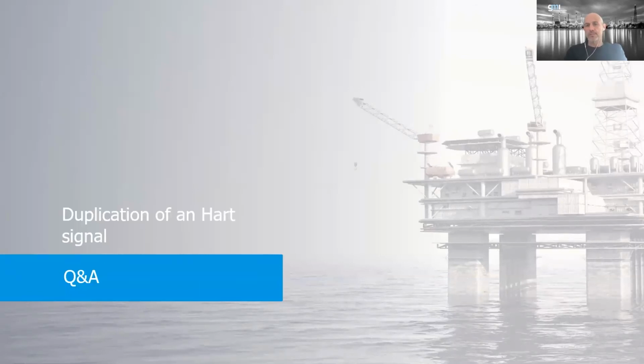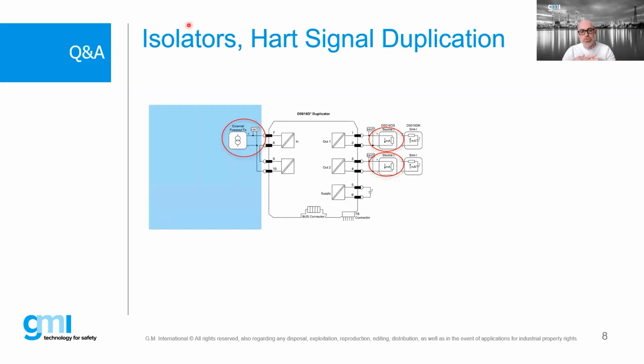Massimo, you want to talk about this? Yes, okay. Another typical question is duplication of the HART signal. Also with regard to devices useful for signal redundancy, such as signal duplicators or splitters, it's possible to obtain compatibility with the HART protocol. GMI offers solutions that allow splitting the HART signal to both outputs of a duplicator device. GMI developed a device that duplicates the 4-20 milliamp signals as well as the HART signals. This device is particularly useful in applications where system redundancy is required.